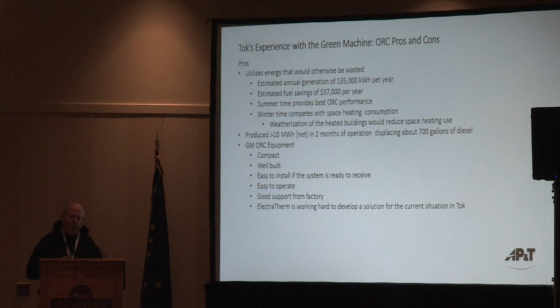On the negative side, yeah, I think we've talked about all of those, but there are some things. The machine does not work without some expense. You have an increase in your parasitic loads. The pumps that move the fluid through the systems have to be, the kW that goes into the pumps has to be taken away from the kW that is produced by the machine. It's a balancing act.